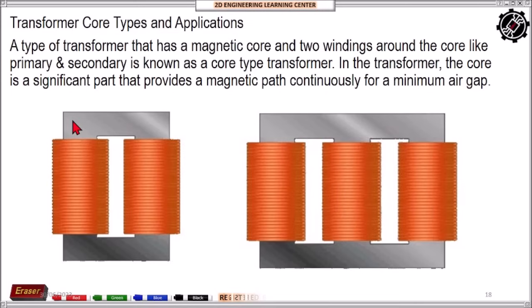So here is its construction. Depending on the arrangement of the winding, it can be toroidal like this or circular like this. This is our low voltage winding or primary winding, and this is our high voltage winding. This is the laminated core - in some, it's inside, with the laminated core wound here. This is usually used in electronic transformers and can also serve as an isolation transformer.